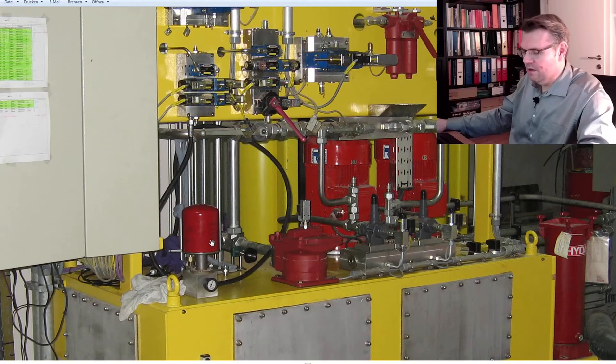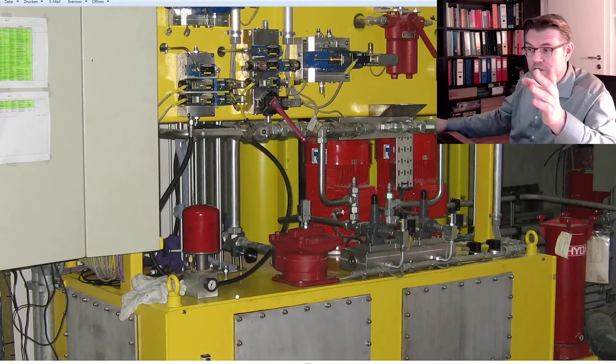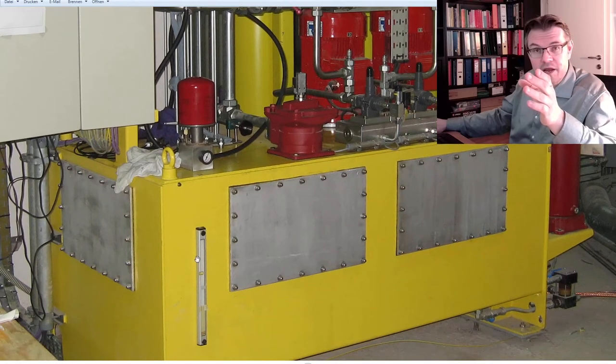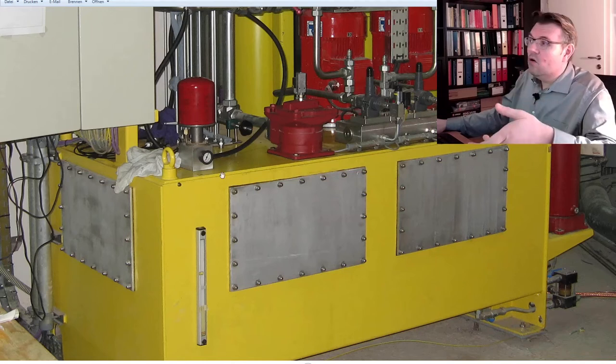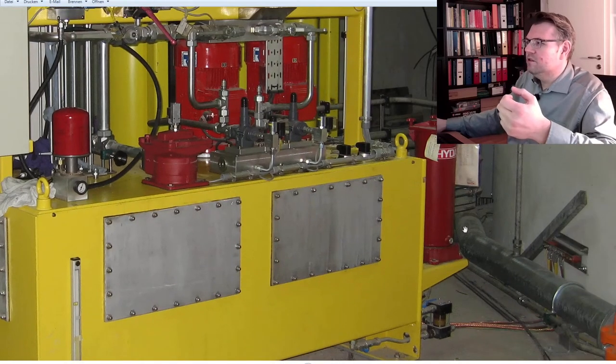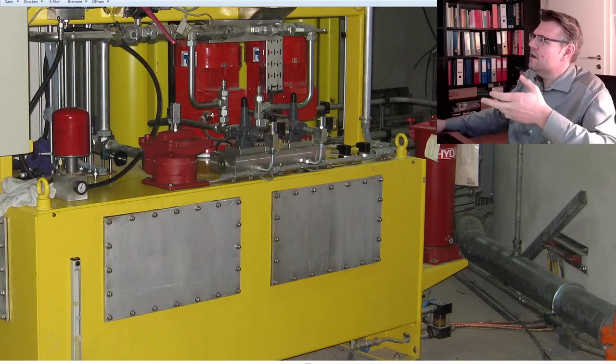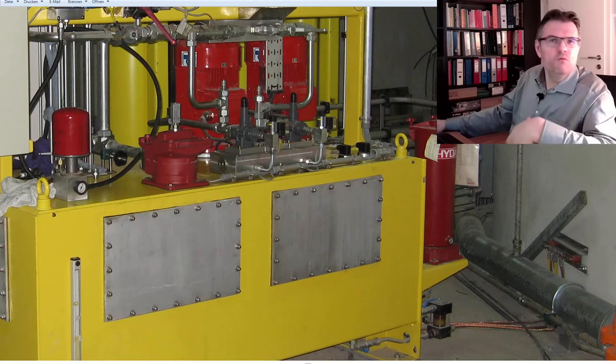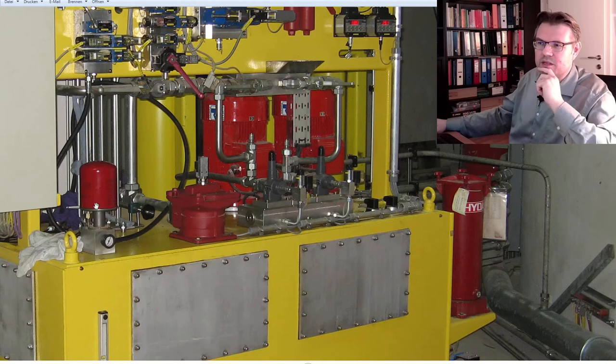Then this thing here, this red thing here, this is actually a filter, an air filter. We also talked about this air filtration, because the level of the oil here will change. So we need to suck in air or get rid of air. And this is done by a filter, because I do not want... You see, it's a dusty environment. Here is a lot of dust. Okay, that's during construction time. However, who says that somebody is not putting up here new things, drilling holes and so on, and then I'll suck in the dirt? No. This is why it needs to be filtered. It needs to be filtered. So this is an air filter.